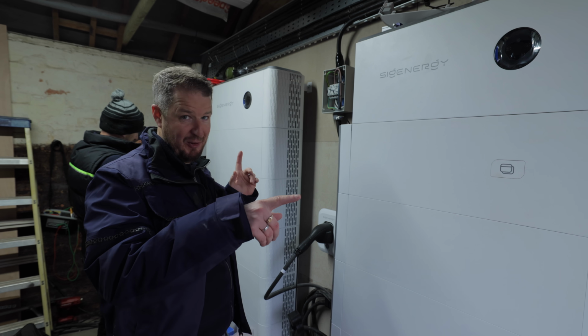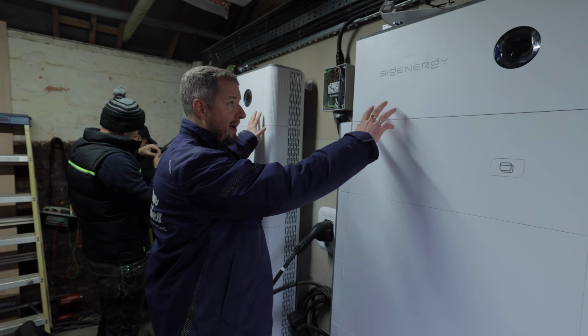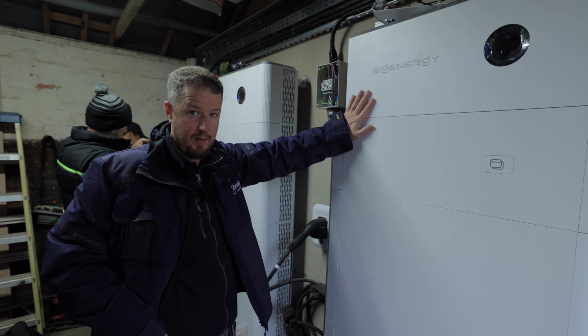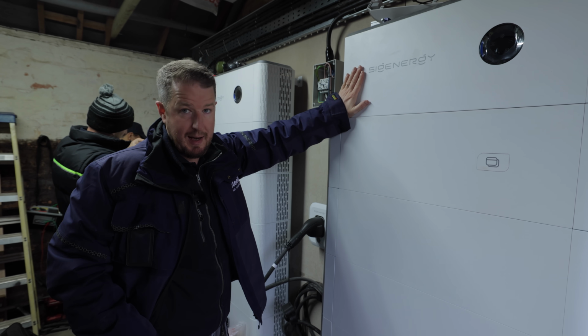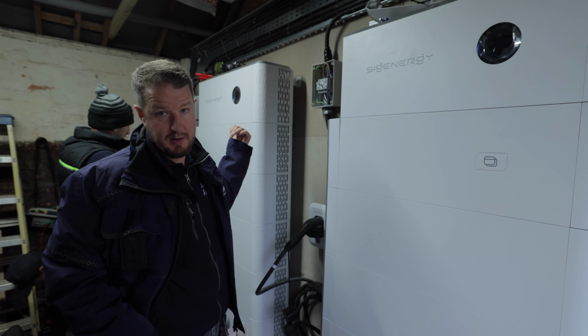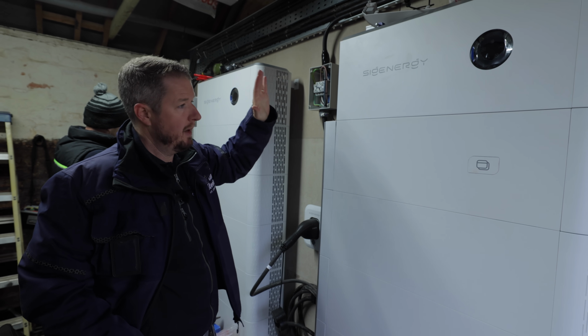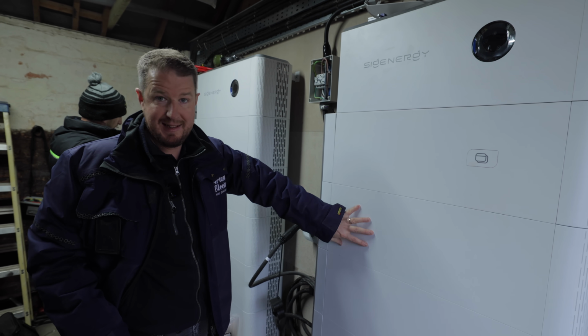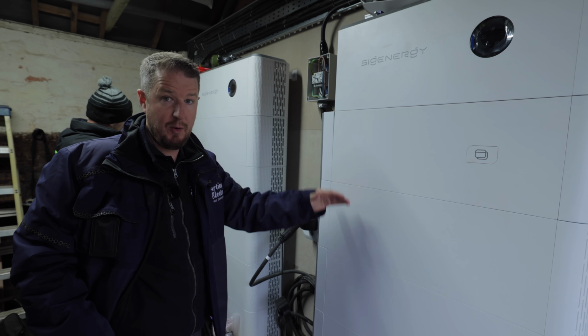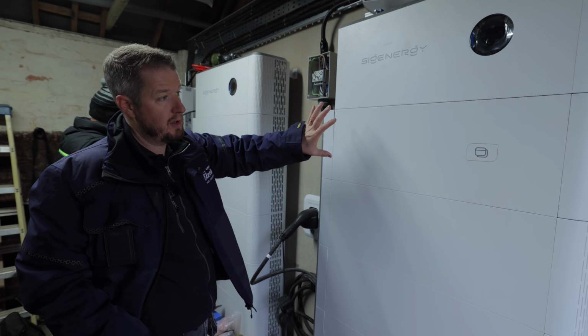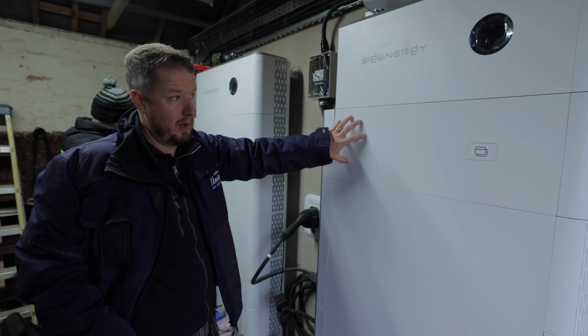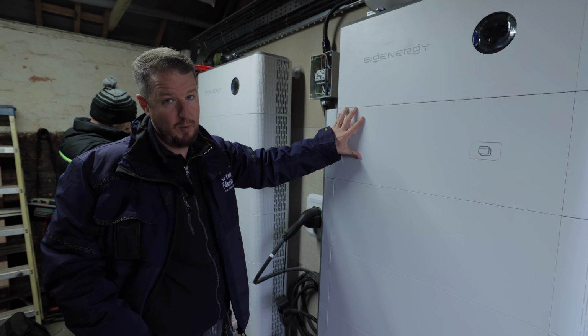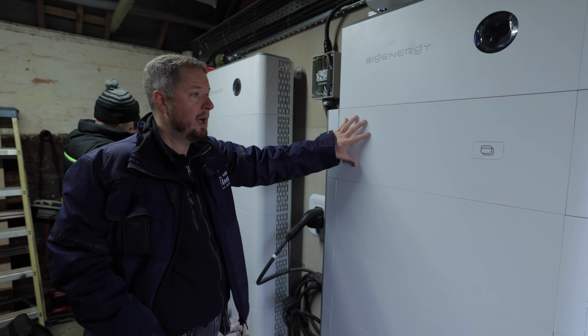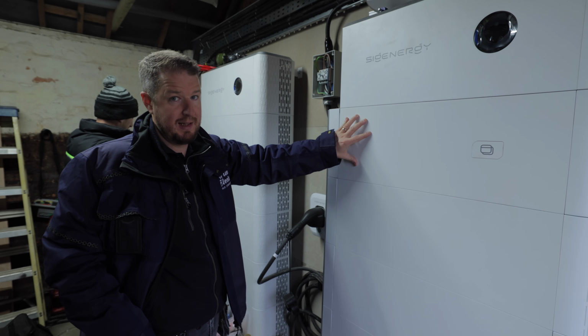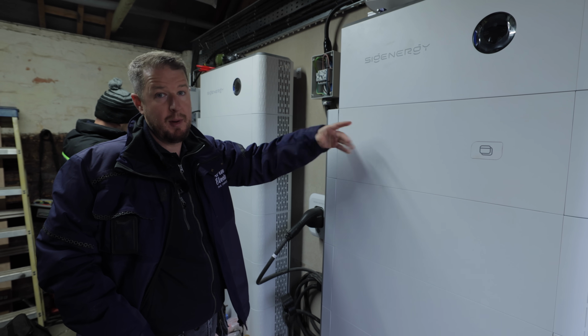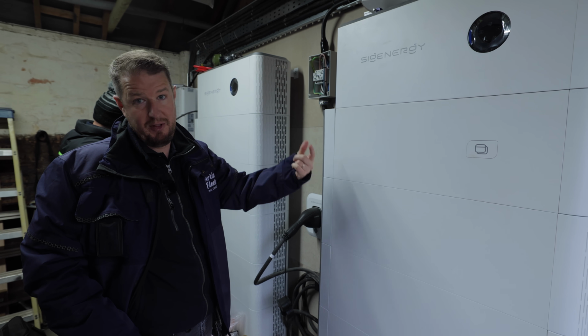So here at the other end of all those cables, we've got our Sigenergy battery inverters. Each of these is a 15 kilowatt inverter, but we've not got solar connected to these - as mentioned, we've got a SolarEdge inverter for a good reason. Each of these modules is an 8 kilowatt hour battery module. In this stack we've got 5, so that's 40 kilowatt hours of storage. Then we've got the DC EV charger, which we'll do a separate video on, but essentially it's a 25 kilowatt DC rapid charger, and it's fully bi-directional ready, so that as soon as vehicle manufacturers open it up, they'll be able to run the house off the car, which is really cool.